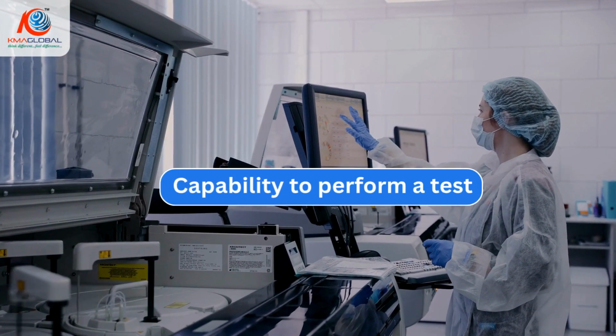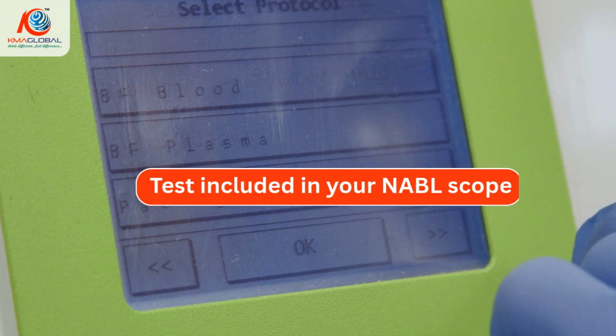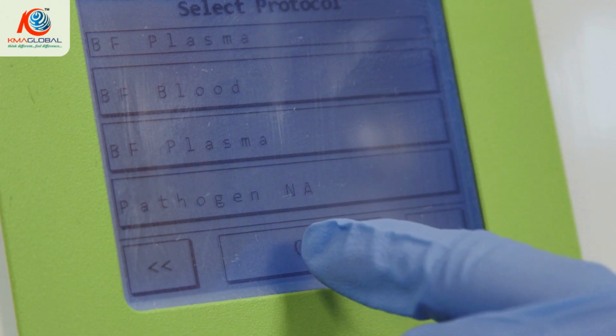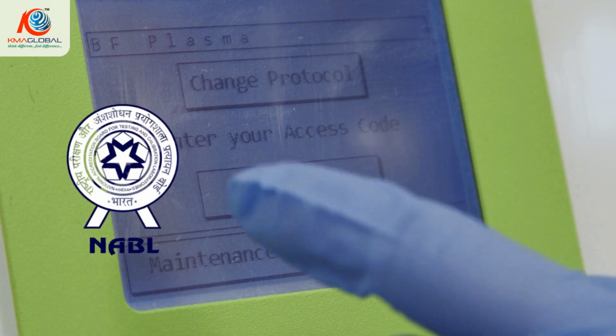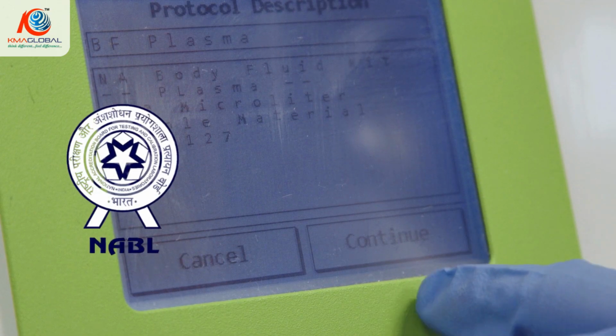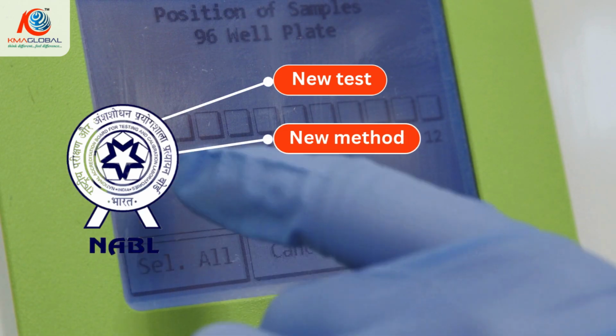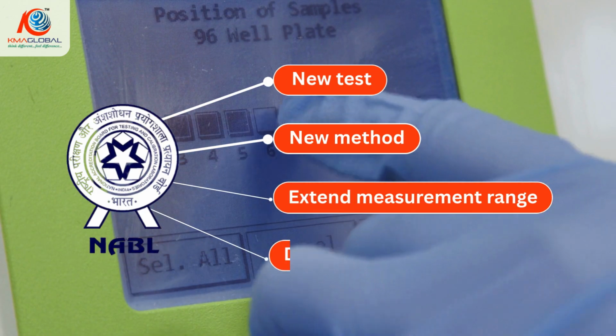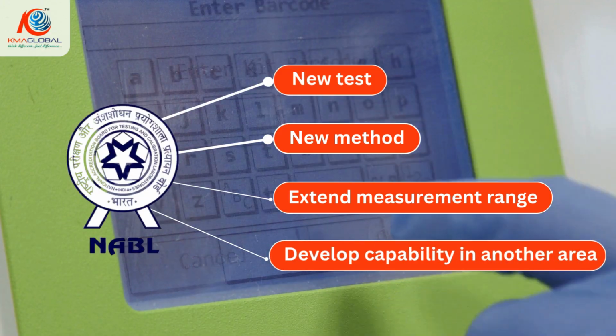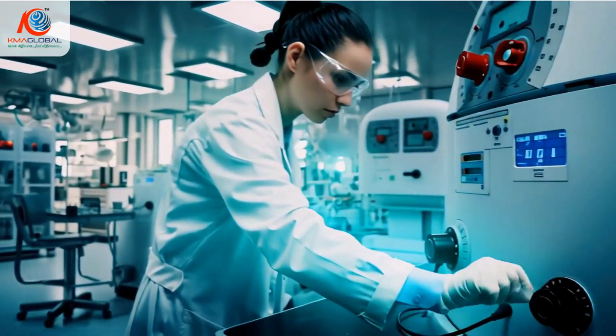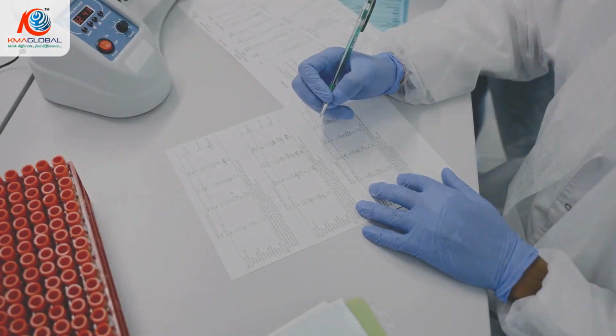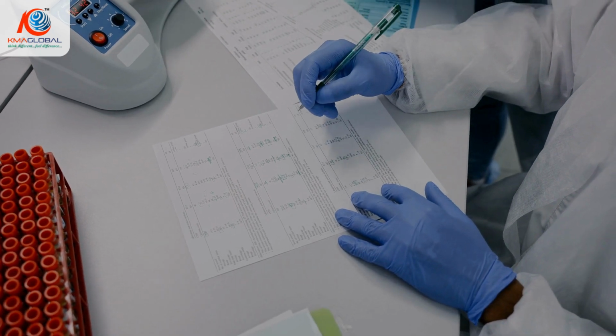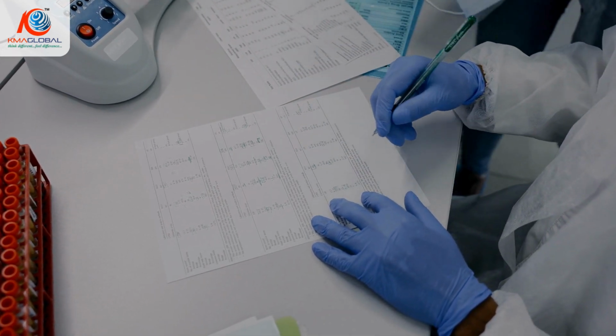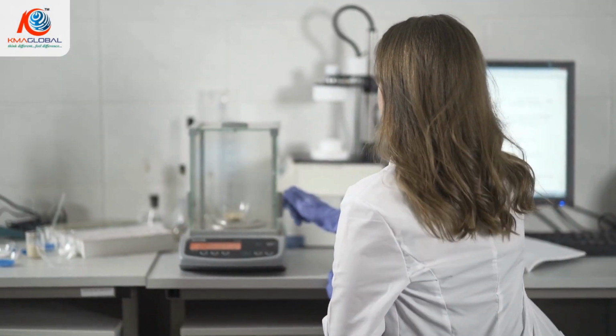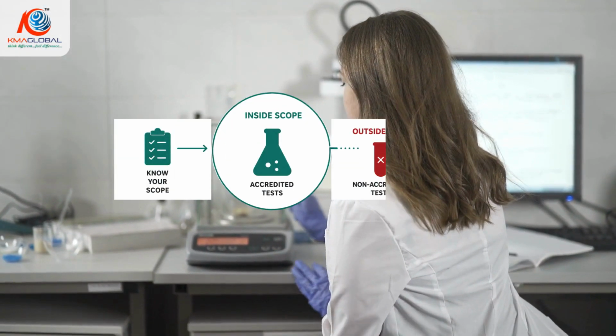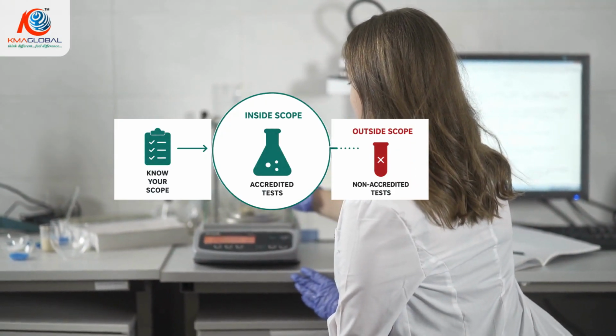So, having the capability to perform a test and having that test included in your NABL scope are two different things. Let's say your laboratory is already accredited for a particular group of tests. Over time, you may add a new test, introduce a new method, extend your measurement range, or develop capability in another area. Your laboratory may be fully capable of performing that activity. But if it is not included in the approved scope, you cannot represent that activity as covered by NABL accreditation. This is why laboratories need to continuously understand what is inside their scope and what falls outside it.